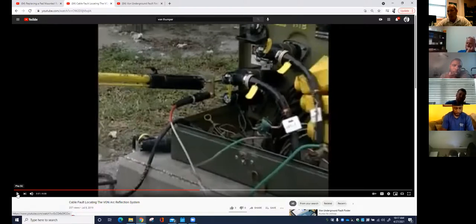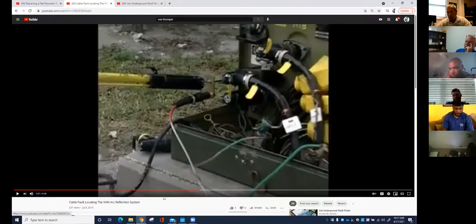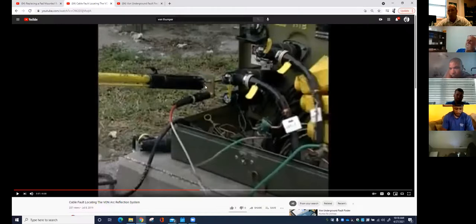Some of these machines will put up a DC voltage of right around 90 kV — that's 90,000 volts DC. When you're in the testing process, as soon as he takes the shotgun off, that's an exposed brass piece of metal right there. Don't be hovering around the transformer, trip or fall, or accidentally make contact with that brass — it's going to be at a very, very high voltage. We had a little bit of a different method — we actually directly connected onto the connector on the end of the cable and were required to wrap all that up in a rubber blanket.